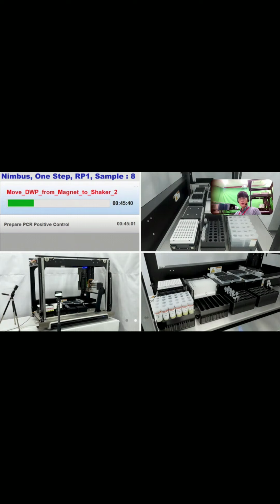And measure the 8 sample positions. If the measured volume is higher than 20 microliter, it means the teaching has to be done. The bottom of the deep well plate, the bottom of the magnet is a little bit higher, so we need to make it go down. Okay, always less than 20 microliter, and put it back. Click the play button icon, and they're going to do this step.